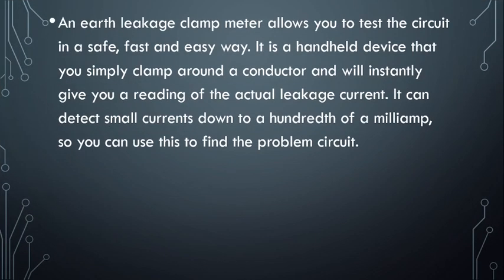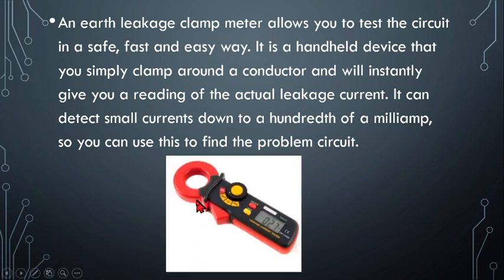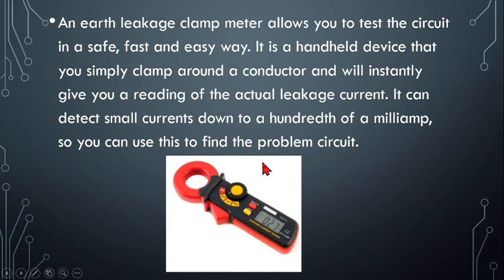Next we have the earth leakage clamp meter, a handheld device that allows you to test a circuit in a safe, fast, and easy way. You simply clamp it around a conductor and it instantly gives a reading of the actual leakage current. It can detect very small currents down to a hundredth of a milliamp. It is used to find leakage current going to the ground, which can cause electric shock and other faults in the system.